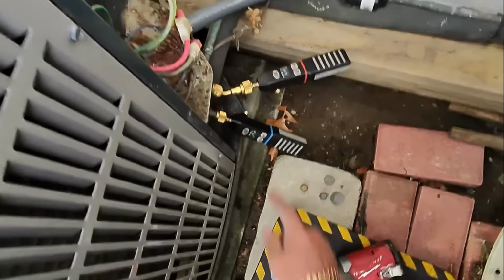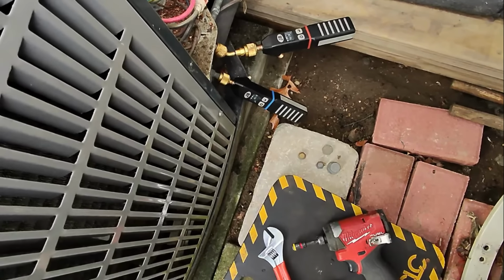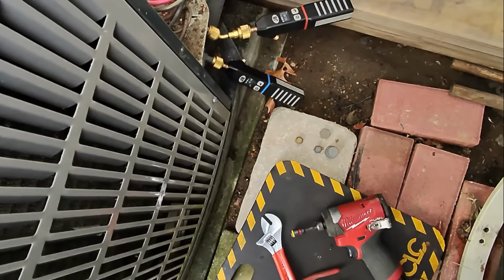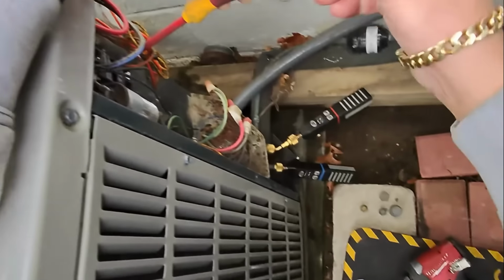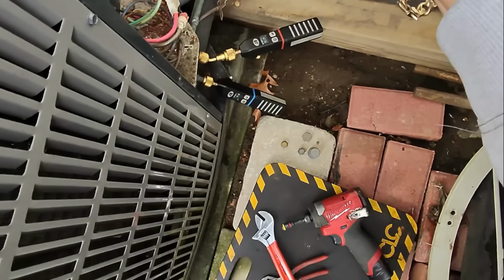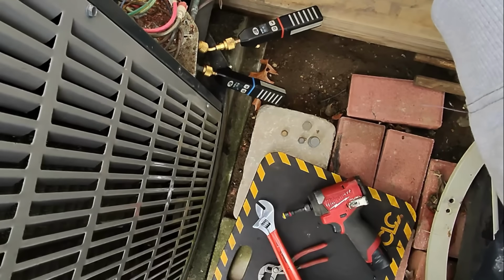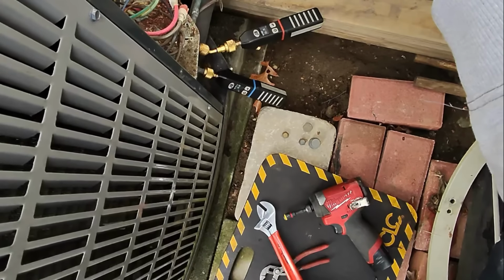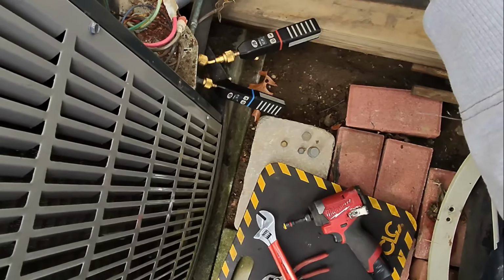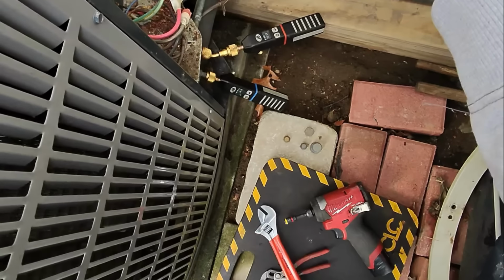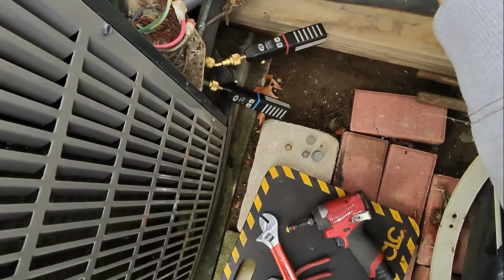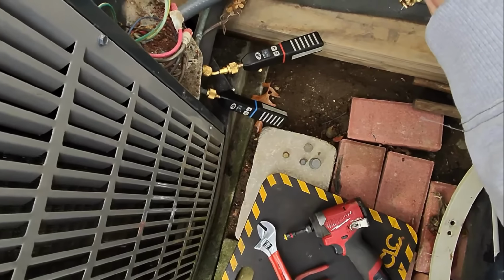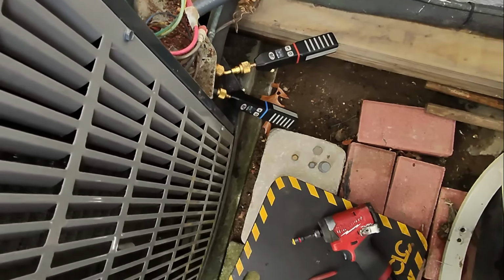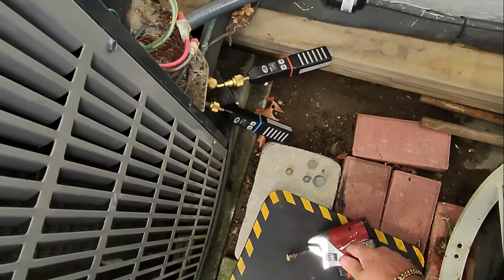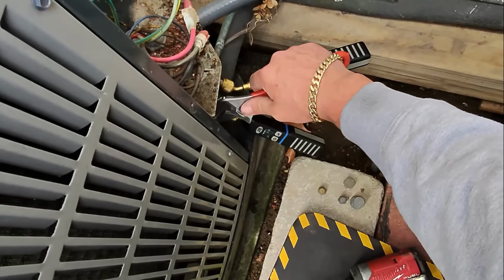Okay, that service valve's closed. 44, 43, 42. Hopefully she can pump down. I would really love it if she pumps down. 39. It's going slowly. 35. We're dropping much quicker now. 30. This is PSI. 25 PSI. 20 PSI. 18, 15, 13, 10, 8, 5, 4, 2.